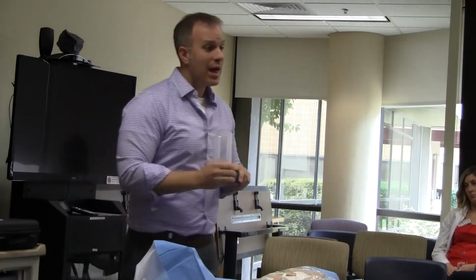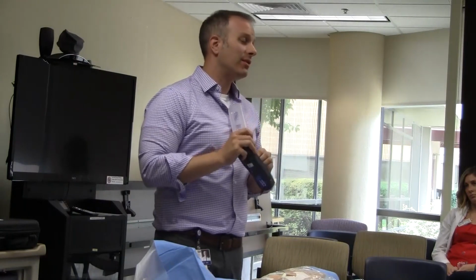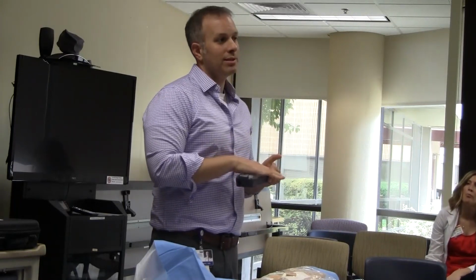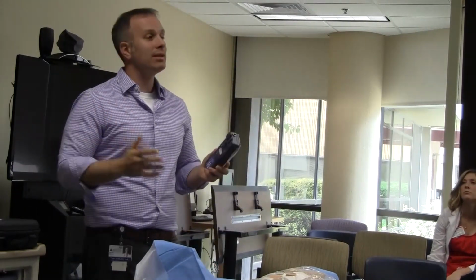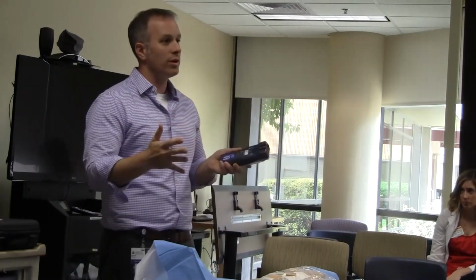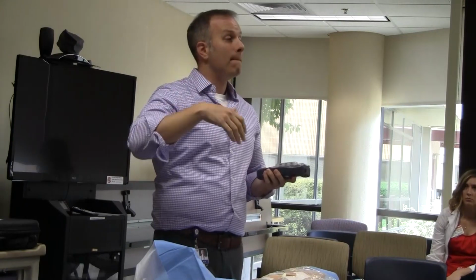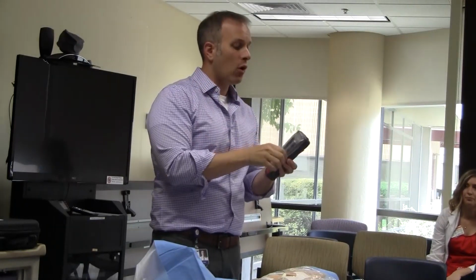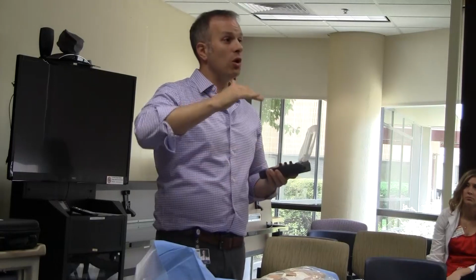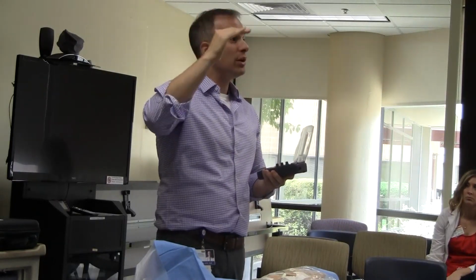So once you have that, then the question is sensitivity. Sensitivity is probably one of those things I probably wouldn't mess with too much. I'd probably just leave it on the base settings of 2. Unless somebody's got an intermittent slow rhythm, and you want it to sometimes sense and sometimes pace, then you'd have to make it more sensitive, so bring the number all the way down, and then slowly make it less sensitive, until it no longer is seeing the heart rhythm and is just pacing all the time.